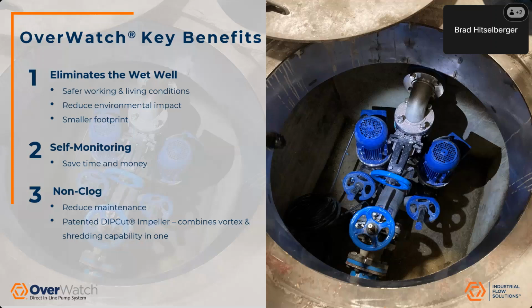Again, this is self-monitoring, so all the telemetry and communications are built into the panel. All the signals can be sent up to whatever SCADA system they have or however they need to be notified. Any of the signals can be sent that they want to monitor. And then again, it's non-clog, so it's going to be really, really good for those retrofit situations if there is a pump station out there that they're having to send work crews out to declog. This thing will basically be passing 1 or 2 wipes at a time instead of passing a bunch of wipes. It's eliminating the fats, oils, and grease layer, and then it's able to react if it does need to react and go into reverse to shred up anything that is in the pump's volute.